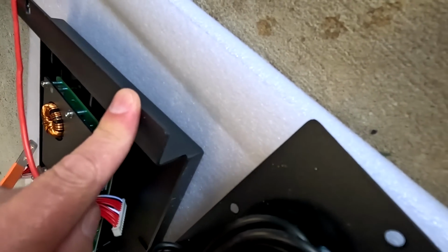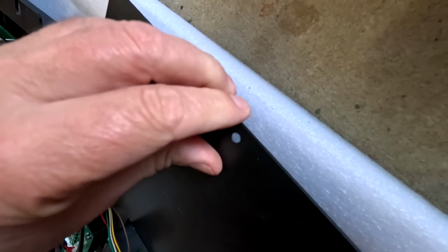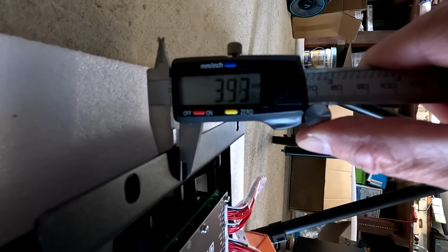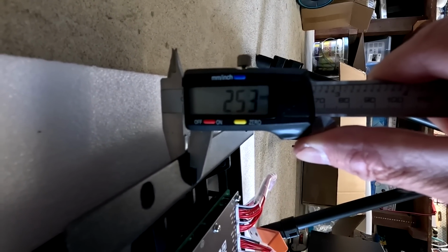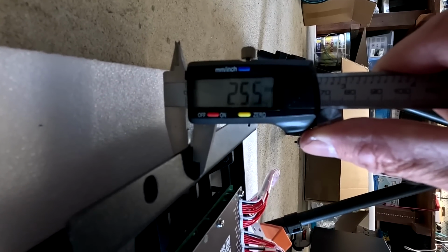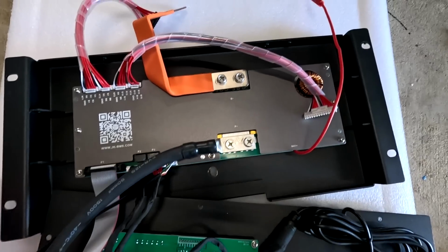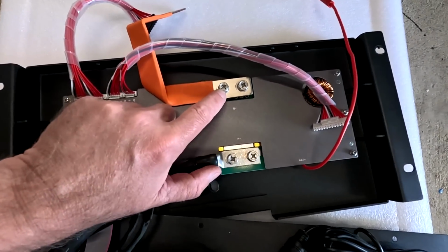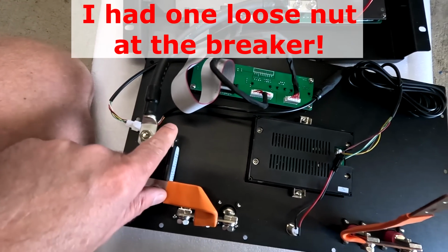And also the compression plate is made from a much thicker metal than, for example, the front plate. Alright, what do we have here for the compression plate? 2.5 millimeters of steel. Nice. All the cables are nicely wrapped and secured. The only thing I'm really missing here are the pen markers on these connectors to ensure someone has checked all these connections again.